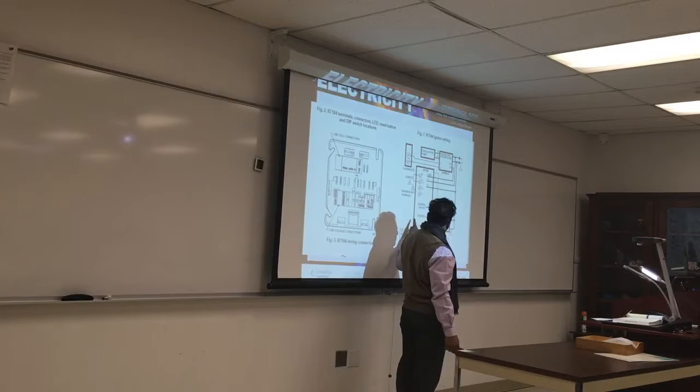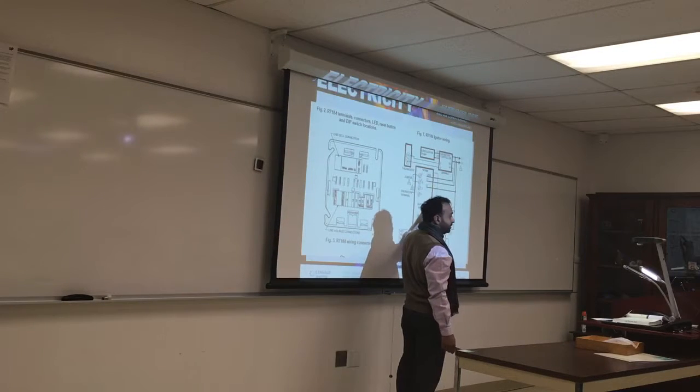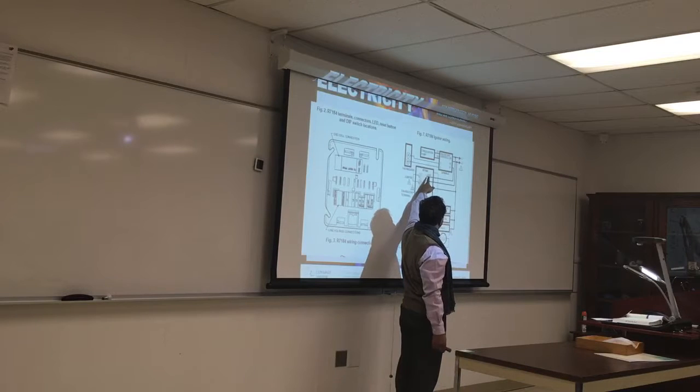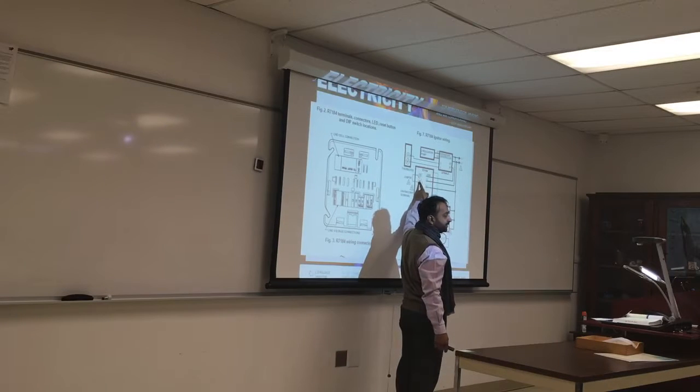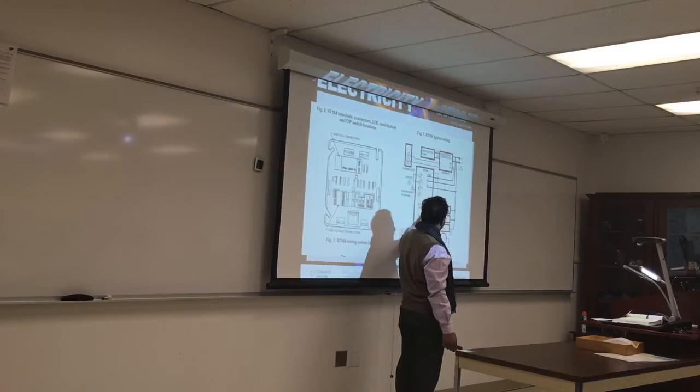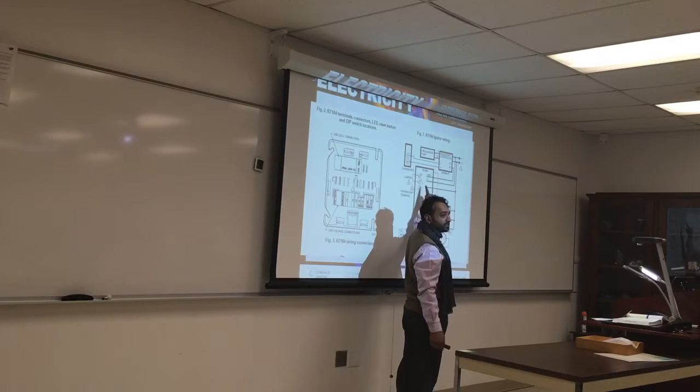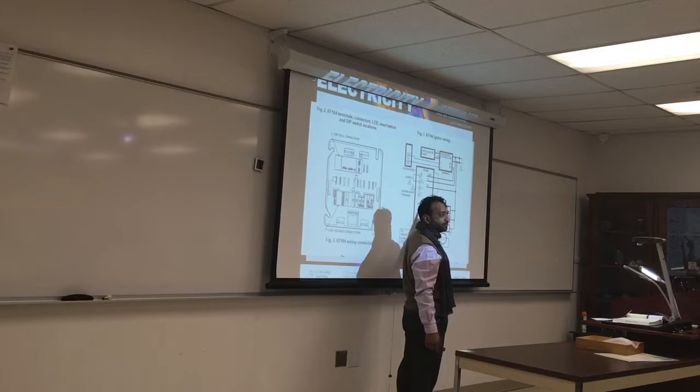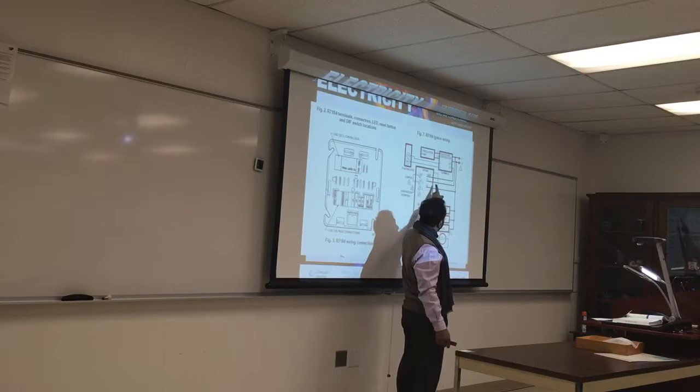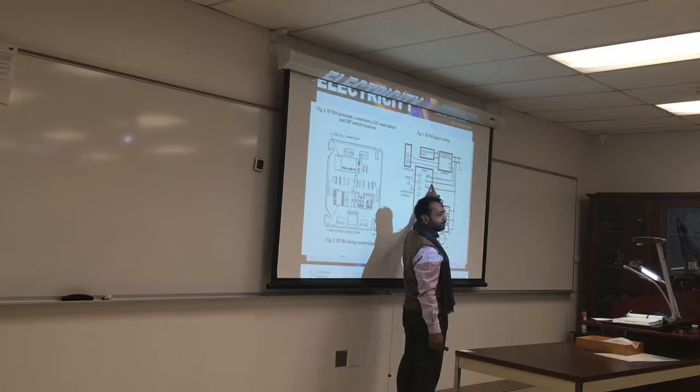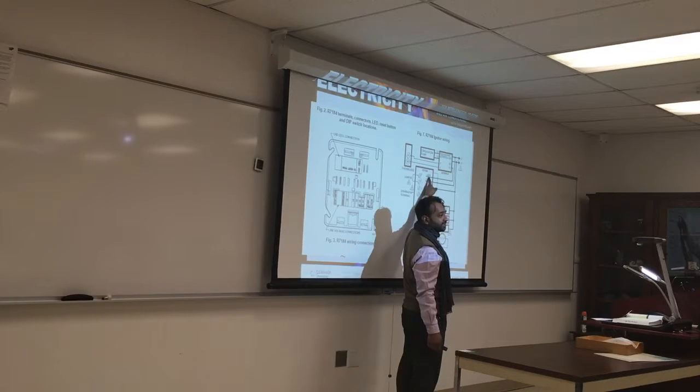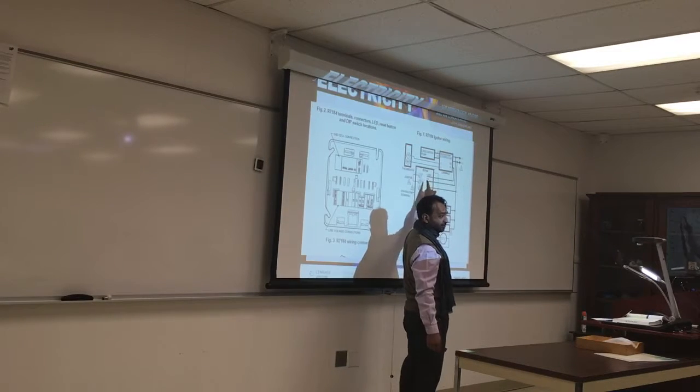One of them will power a relay inside, and this also has a transformer in it. So there's a relay here inside that will activate and connect the burner motor to the L1 power. So all the power coming here is 110, supplied by the line voltage. The limit is just decision-making power. It's 110.